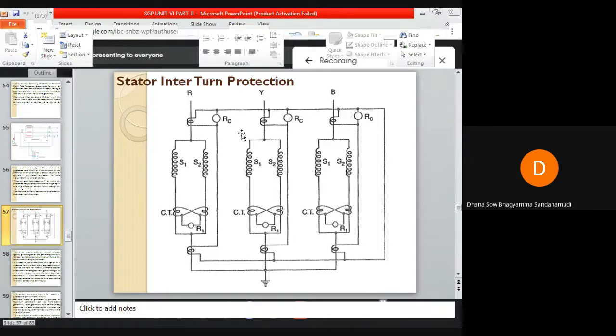These are the relays. R1 and RC are both relays. RC relays are for protecting the windings against phase-to-phase and phase-to-earth faults. R1 relays are for protecting the windings against interturn faults. If you observe, in each phase the whole winding is divided into two windings, S1 and S2, and to each winding the primary of a CT is provided. Their secondaries form a closed loop, and the secondary terminals of these two CTs are given to a relay R1.